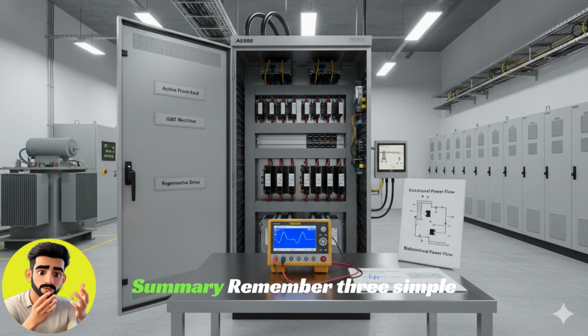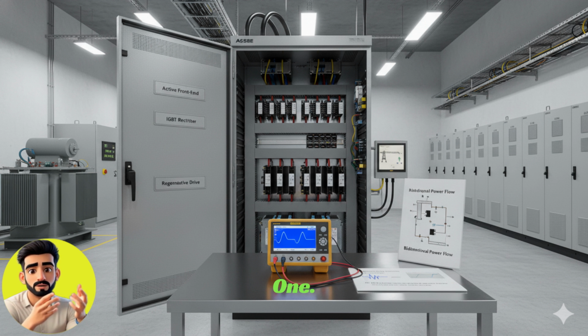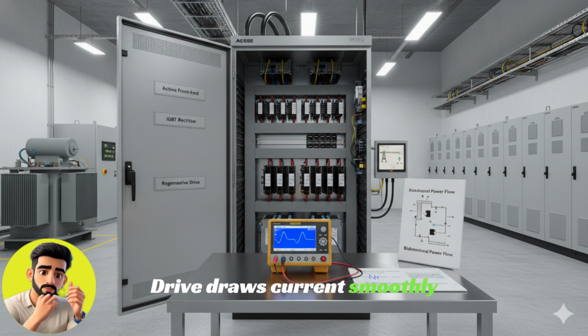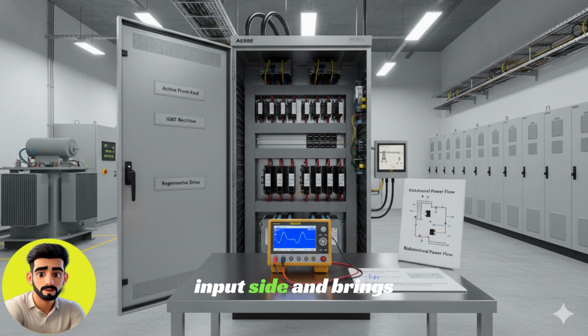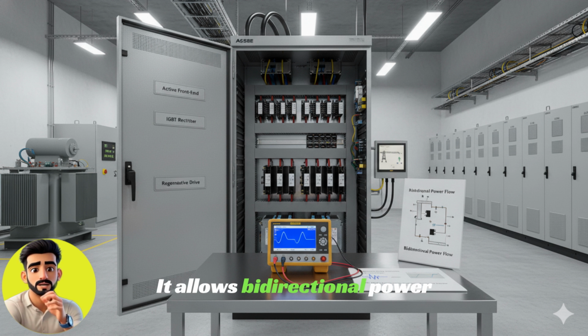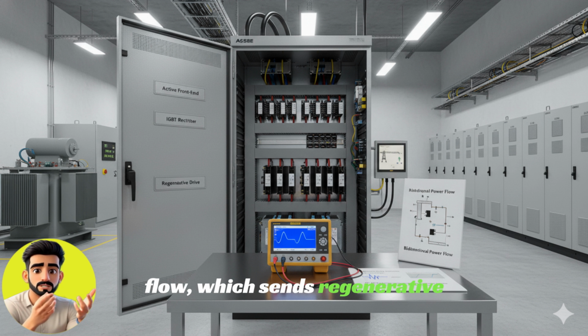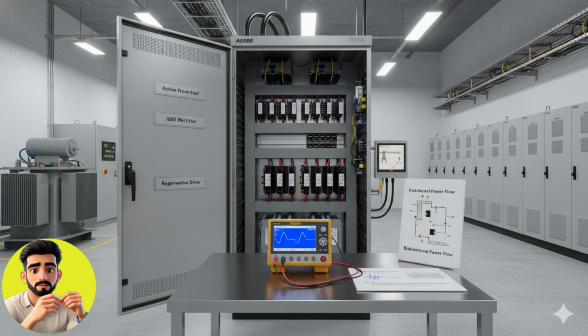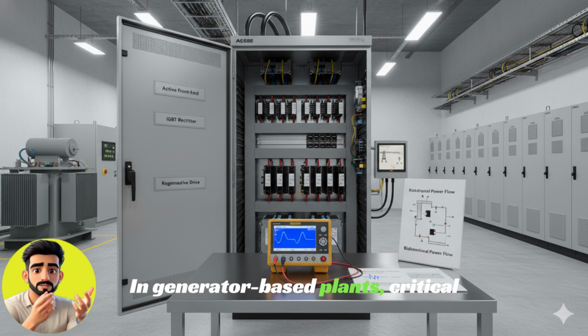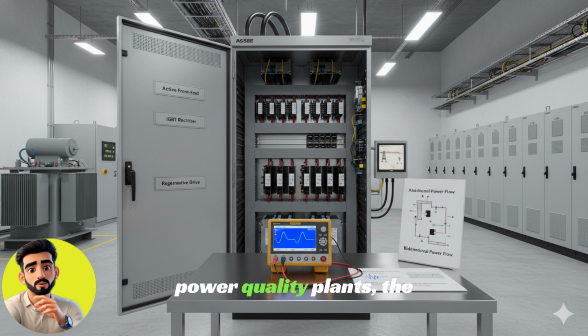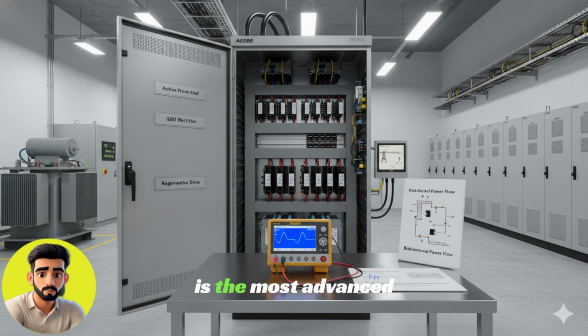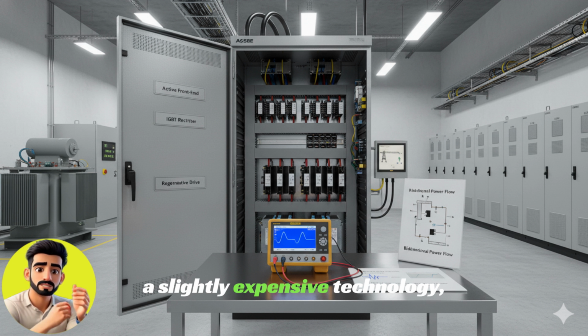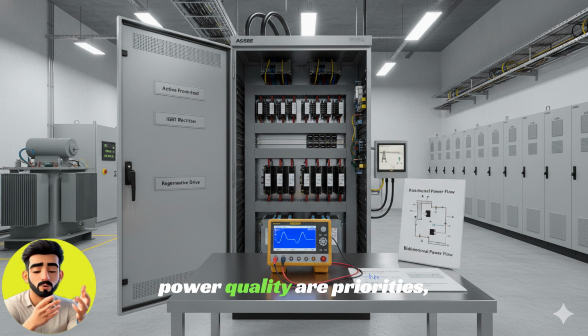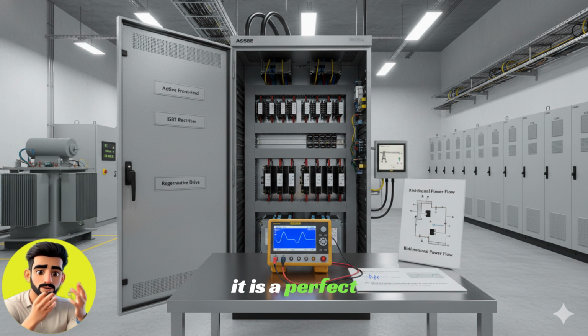Summary. Remember three simple points. 1. The AFE drive draws current smoothly and controlled on the input side and brings harmonics close to zero. 2. It allows bidirectional power flow which sends regenerative energy back to the grid. 3. In generator-based plants, critical process plants, and strict power quality plants, the AFE drive is the most advanced and safest choice. AFE is a slightly expensive technology, but where stability and power quality are priorities, it is a perfect long-term solution.